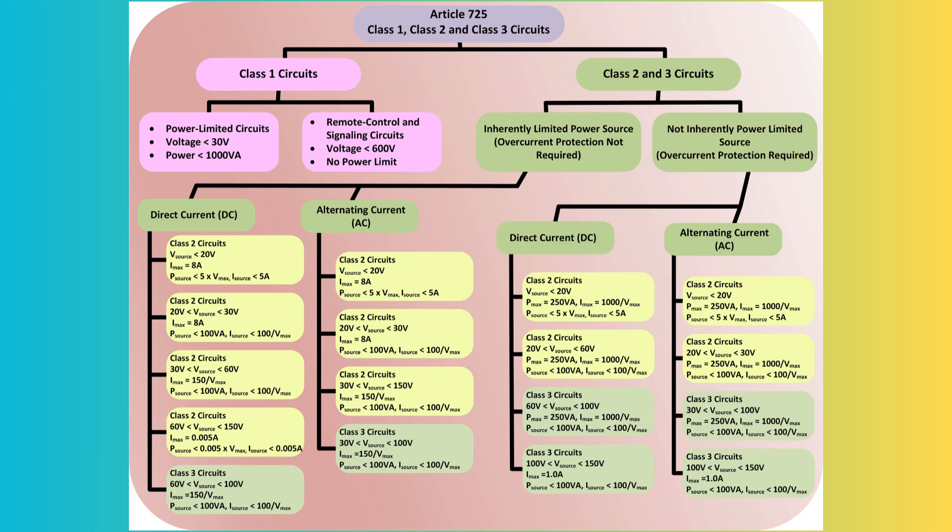Article 725 outlines several requirements for Class I, Class II, and Class III circuits. Class I circuit conductors can share a cable, enclosure, or raceway with power supply circuits only when the equipment they power is functionally associated with the Class I circuit. Multiple Class I circuit conductors can be housed in the same cable, enclosure, or raceway.